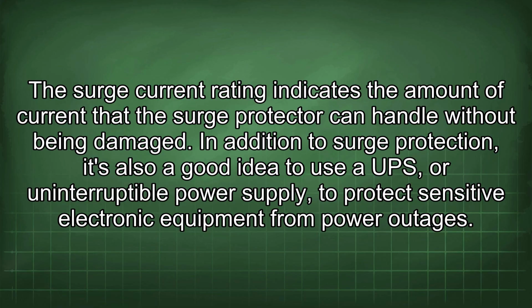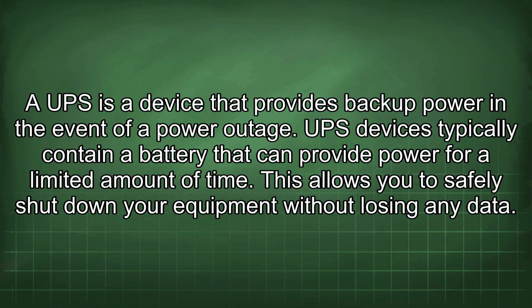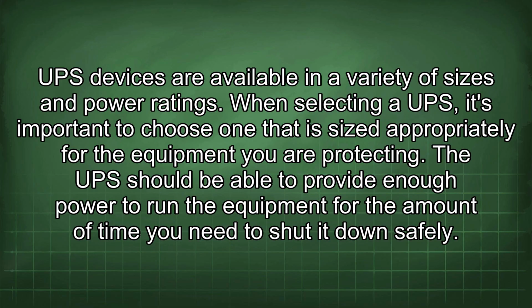In addition to surge protection, it's also a good idea to use a UPS or uninterruptible power supply to protect sensitive electronic equipment from power outages. A UPS is a device that provides backup power in the event of a power outage. UPS devices typically contain a battery that can provide power for a limited amount of time. This allows you to safely shut down your equipment without losing any data. UPS devices are available in a variety of sizes and power ratings. When selecting a UPS, it's important to choose one that is sized appropriately for the equipment you are protecting. The UPS should be able to provide enough power to run the equipment for the amount of time you need to shut it down safely.